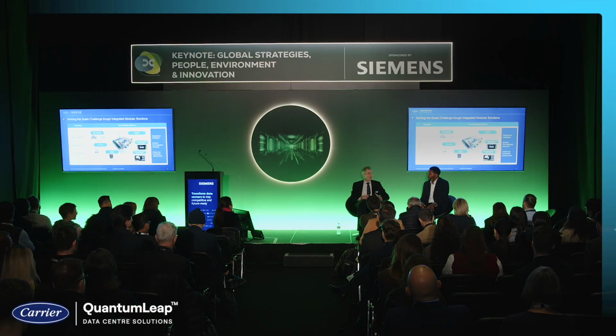So this density and scale oblige us, as partners in data centers, to rethink the building process. We used to provide chillers, somebody else used to provide piping, some valving, some strainers, etc., and then somebody was checking everything is okay, commissioning, looking at the leaks, etc. Today, when we have 200 megawatts, 500 megawatts, 800 megawatts, the number of chillers and elements becomes huge. You need to be able to reduce commissioning time and installation time by a factor of 2 or 3.